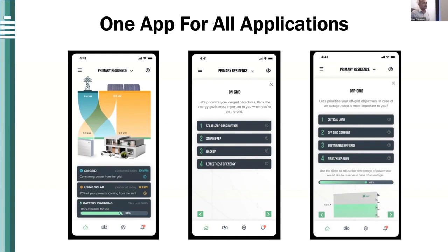What is the voltage of the high voltage system? It really ranges depending on how many battery units you have per stack. On the low range it starts at 119 volts, and on the high range it'll go all the way up to 315 volts if you have 6 of the 4.9 kilowatt-hour battery packs, or 29.4 kilowatt-hours total.